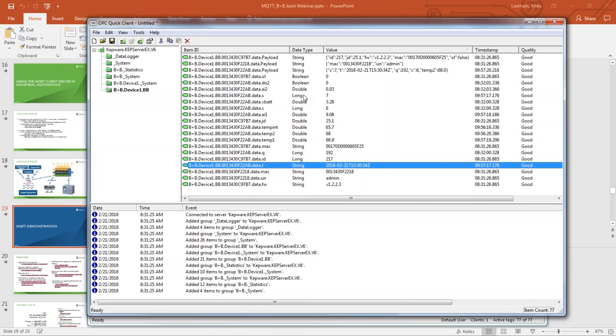A clarifying question: KepServer is talking directly to the gateway, not the cloud. In the B&B platform, that gateway has a built-in broker. The typical architecture is KepServer installed locally in the facility on the same network, connecting directly to that broker. If you want cloud connectivity, you can do that either directly to the broker or through KepServer. The gateway also supports GSM/GPRS fallback.